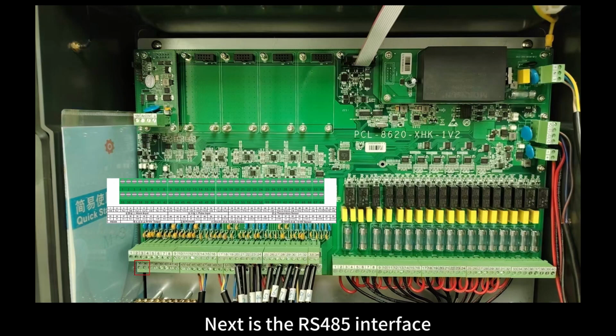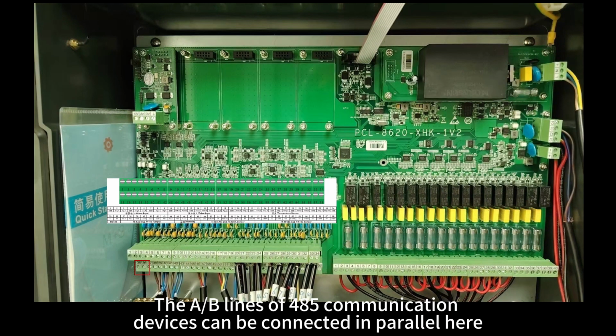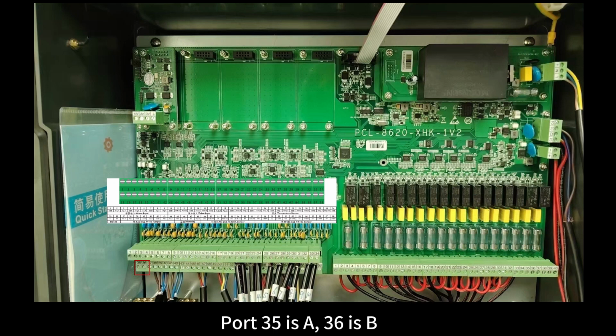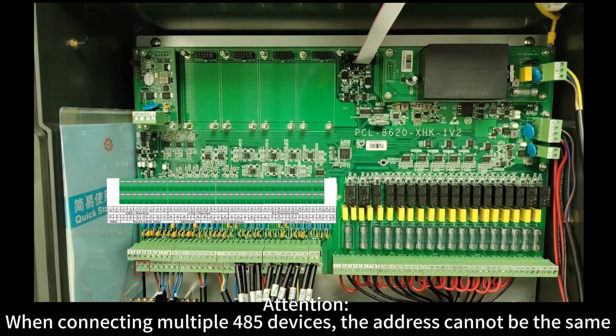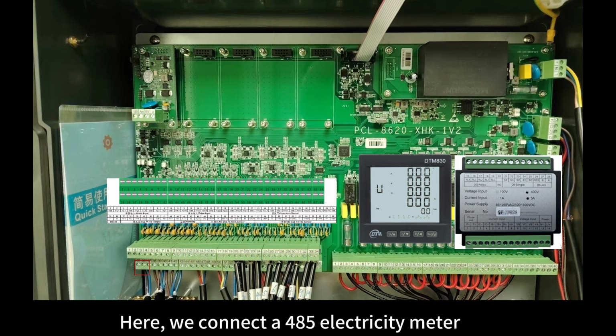Next is the RS485 interface. The A-B lines of 485 communication devices can be connected in parallel. Here, port 35 is A, 36 is B. Attention! When connecting multiple 485 devices, the address cannot be the same. Here, we connect a 485 electricity meter.